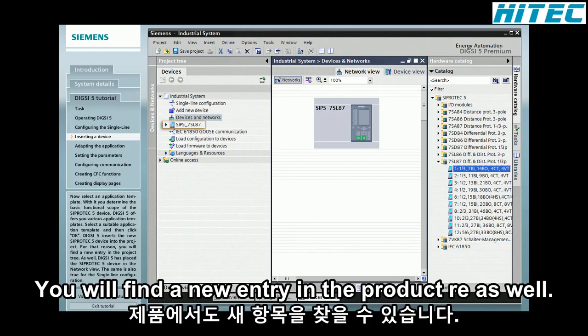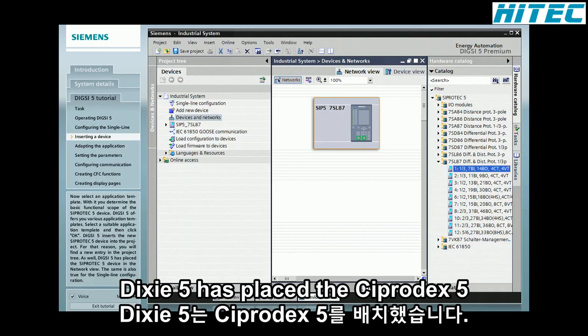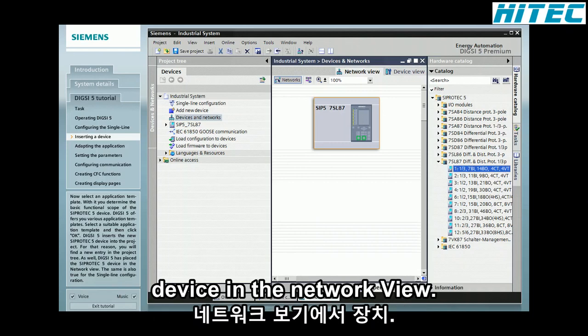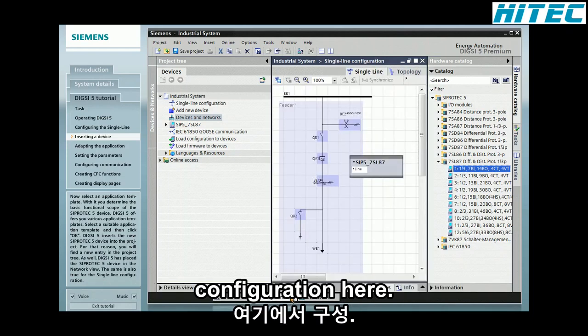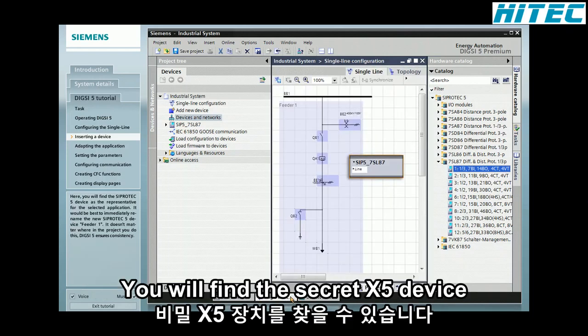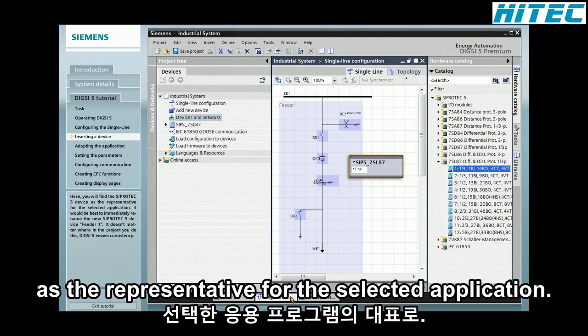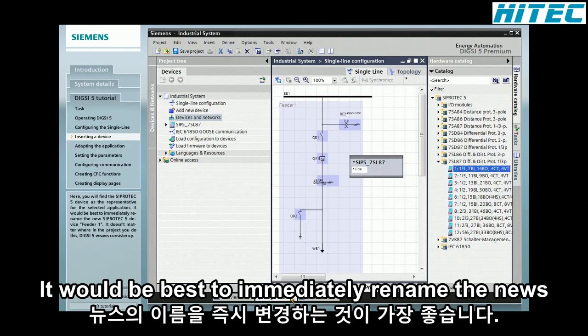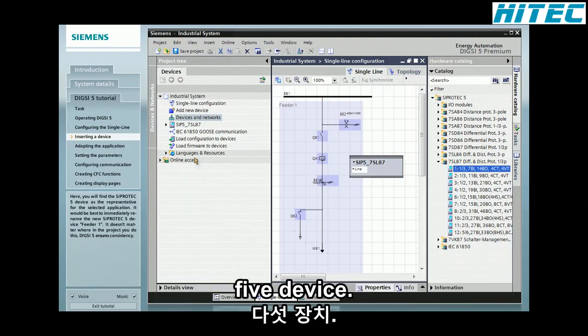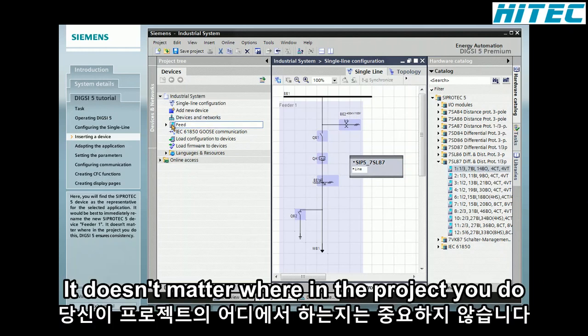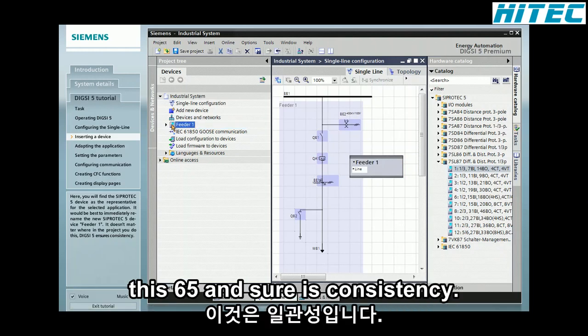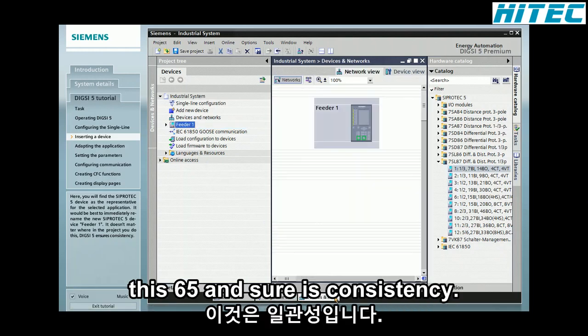For that reason, you will find a new entry in the project tree. As well, DIGSI 5 has placed the SIPROTEC 5 device in the network view. The same is also true for the single line configuration. Here you will find the SIPROTEC 5 device as the representative for the selected application. It would be best to immediately rename the new SIPROTEC 5 device Feeder 1. It doesn't matter where in the project you do this, DIGSI 5 ensures consistency.